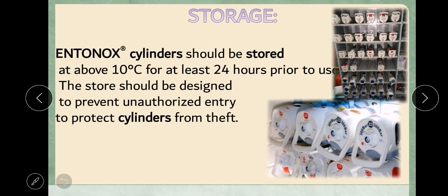Okay. In storage, the Entonox cylinder should be stored at above 10 degrees Celsius for at least 24 hours prior to use. The storage should be designed to prevent unauthorized entry to protect cylinders from theft.